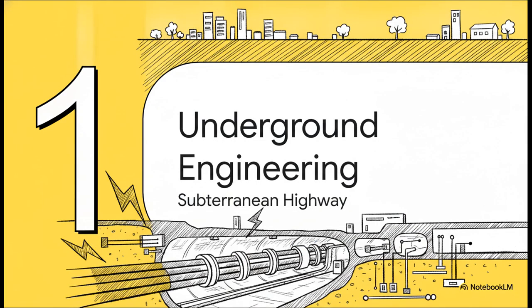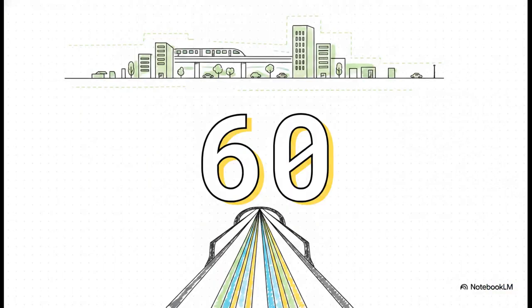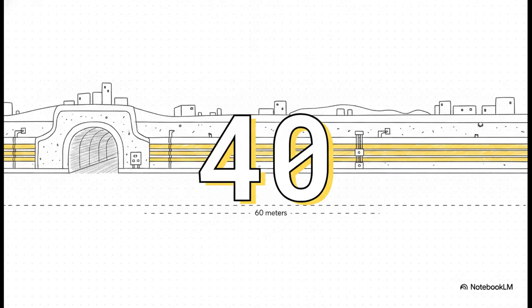Moving into our next section, engineering the underground, Singapore's subterranean highway. Because Singapore is incredibly land scarce, you obviously can't just string extra high voltage cables across the surface of the island. So engineers had to get creative. They went down, exactly 60 meters straight down into the earth. This incredible depth was chosen deliberately to completely remove the transmission network from the reach of virtually all future above-ground construction and even mass rapid transit expansions. Down at that 60-meter depth, they constructed a massive 40-kilometer-long cross-island tunnel system. Think of it as a dedicated subterranean highway designed exclusively to securely house these high-capacity cables, keeping them safe and completely out of sight.